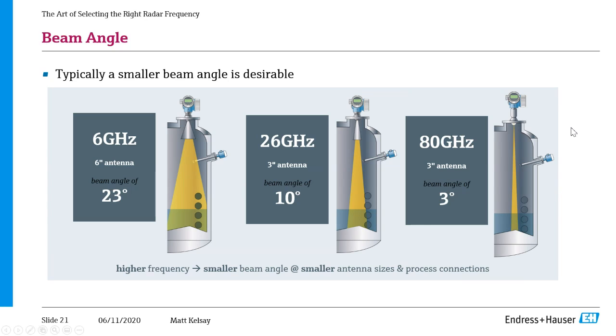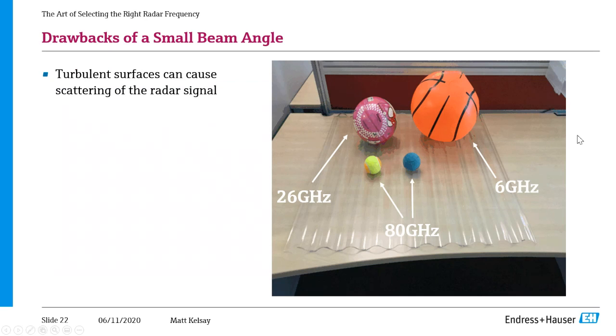So the other thing it allows, that I'll show in a little bit, is much smaller process connections, as you've seen, because we can maintain smaller beam angles. And it also allows us to mount in much taller nozzles because of that small beam angle. There you go to the next. So like I said, typically a small beam angle is desirable.